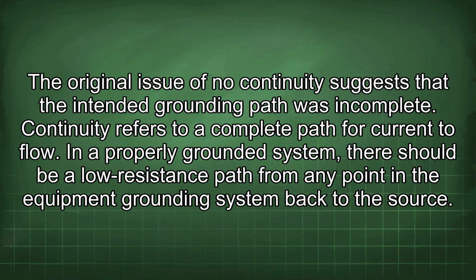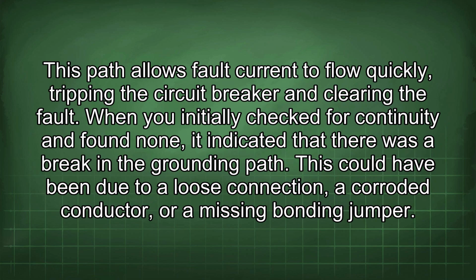The original issue of no continuity suggests that the intended grounding path was incomplete. Continuity refers to a complete path for current to flow. In a properly grounded system, there should be a low resistance path from any point in the equipment grounding system back to the source. This path allows fault current to flow quickly, tripping the circuit breaker and clearing the fault.